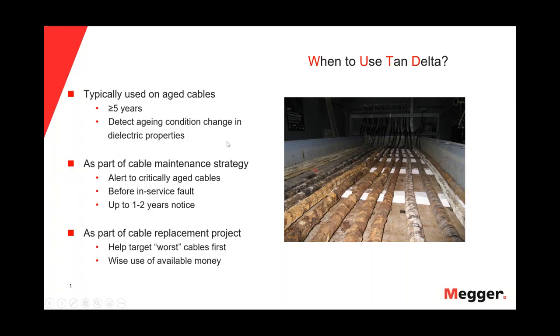It can also be used as part of the cable maintenance strategy. It's going to alert you to critically aged cables before in-service fault, with up to 1 to 2 years notice. It's also going to be used as part of a cable replacement project. Where this comes into play is that it's going to let you target the worst cables first and allow you to make the best and wisest choice of the available money, depending on how valued that asset is, on where you should spend your money first.